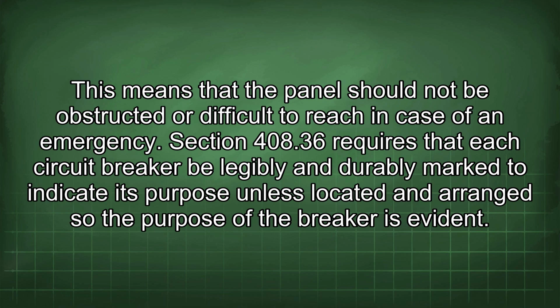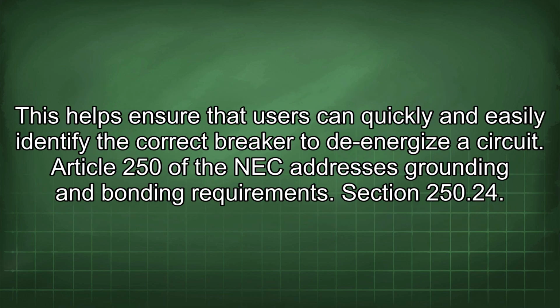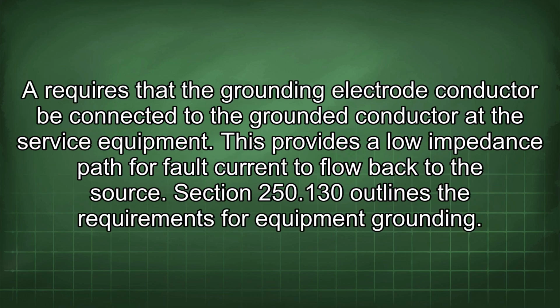Section 408.36 requires that each circuit breaker be legibly and durably marked to indicate its purpose, unless located and arranged so the purpose of the breaker is evident. This helps ensure that users can quickly and easily identify the correct breaker to de-energize a circuit. Article 250 of the NEC addresses grounding and bonding requirements. Section 250.24 requires that the grounding electrode conductor be connected to the grounded conductor at the service equipment. This provides a low impedance path for fault current to flow back to the source.